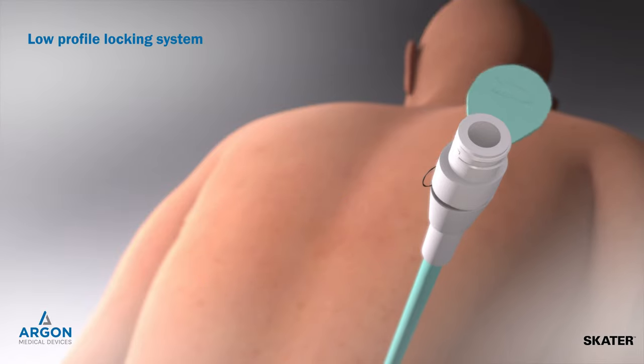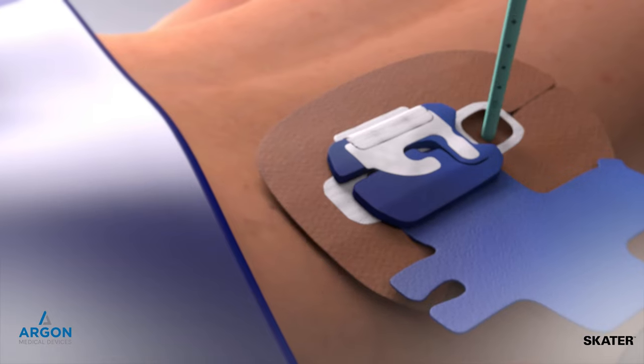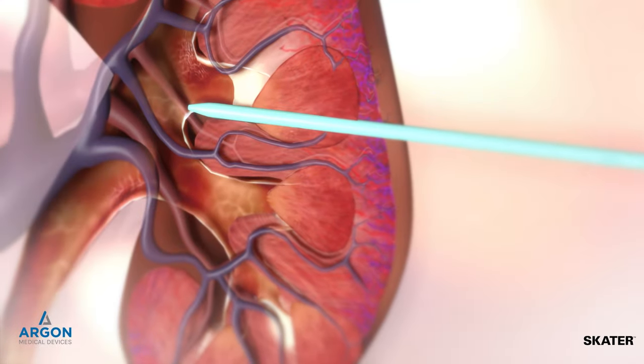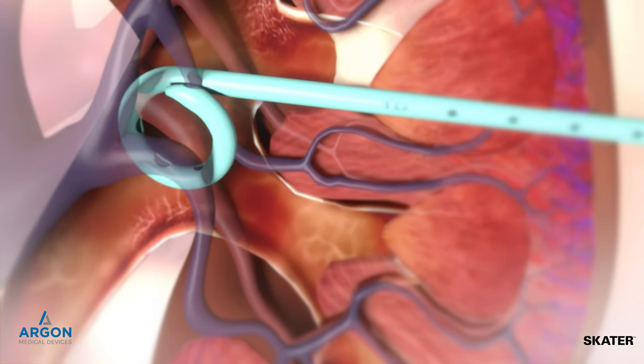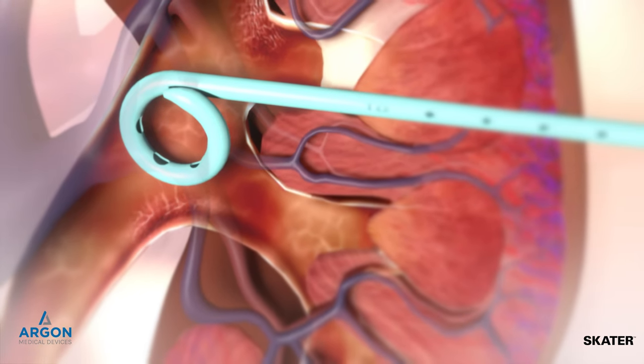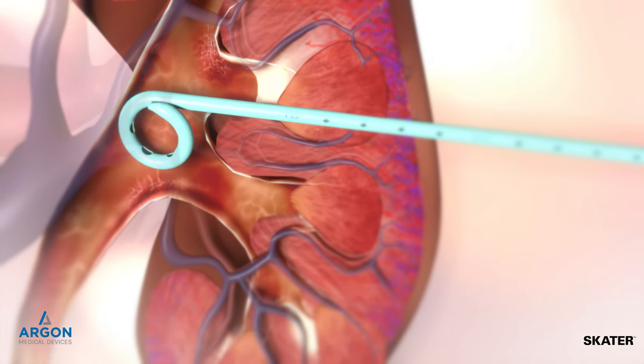The low-profile pigtail locking system with snap-off tab provides further patient comfort. Throughout the procedure, SKATER drainage catheter's large skived holes help maximize drainage. Its highly durable polyurethane construction provides kink resistance and configuration memory, and can be used safely with ethyl alcohol and doxycycline.